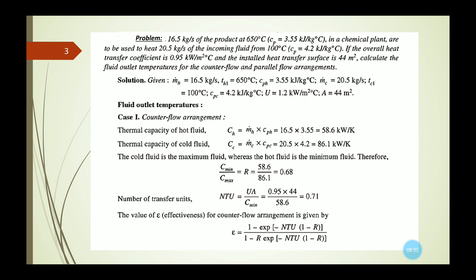Now, what is the value of the NTU, the number of transfer units? The formula is UA divided by C min. U is the overall heat transfer coefficient given in this question, the heat transfer surface area is given as 44, and C min is the thermal capacity of the hot fluid. As all the values are known to us, we can calculate the number of transfer units, it is 0.71.